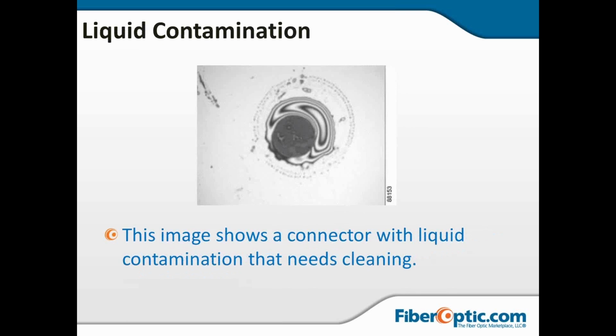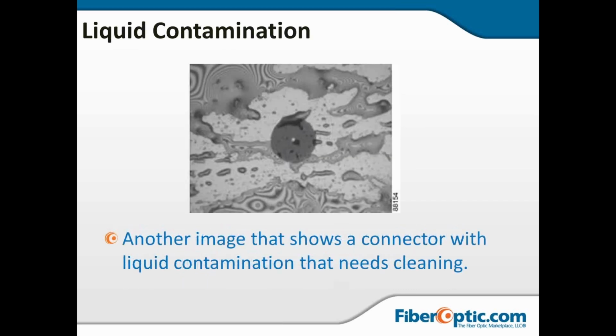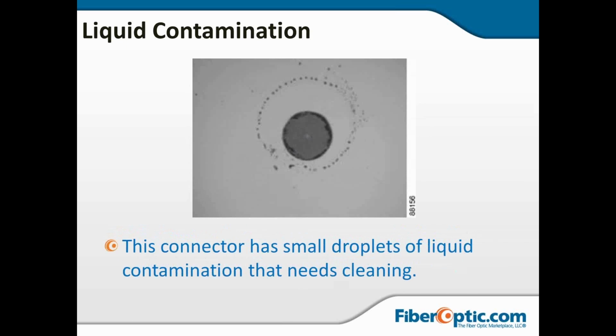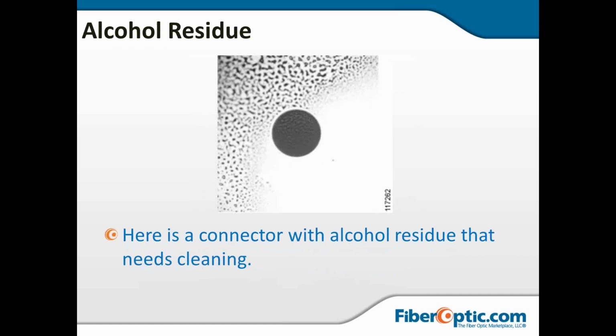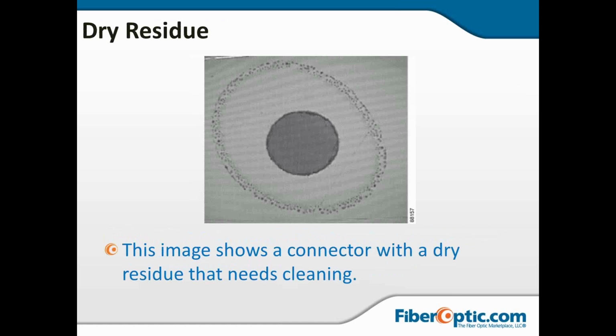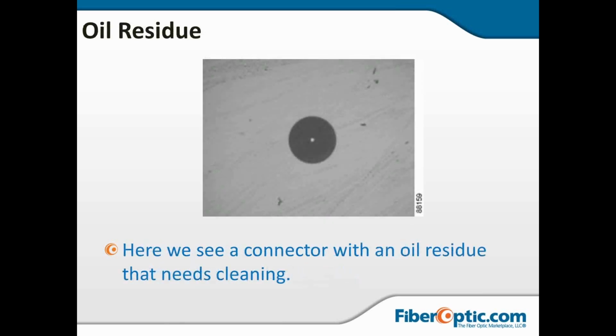This is some sort of liquid contaminant. It just needs to be cleaned. Here's another image that's showing a liquid contaminant that needs to be cleaned. That one looks like skin oil as well. Here's small droplets of liquid. This looks like somebody took a swab and cleaned and didn't dry it out correctly. Alcohol residue. Another looks like a swab signature. This looks like it's dried on there and is residue that needs to be cleaned off. It's probably going to need another wet cleaning before this can be usable.